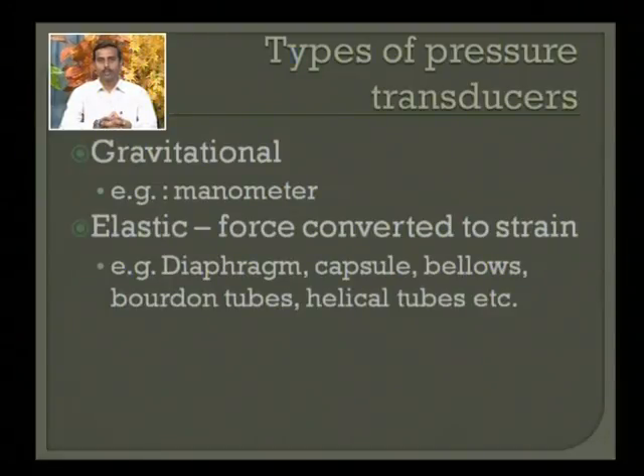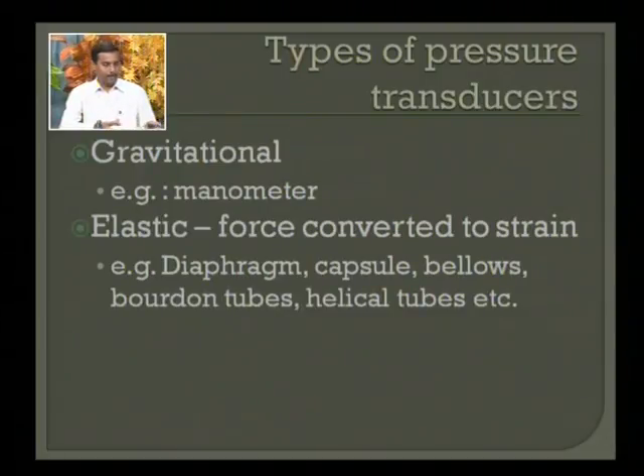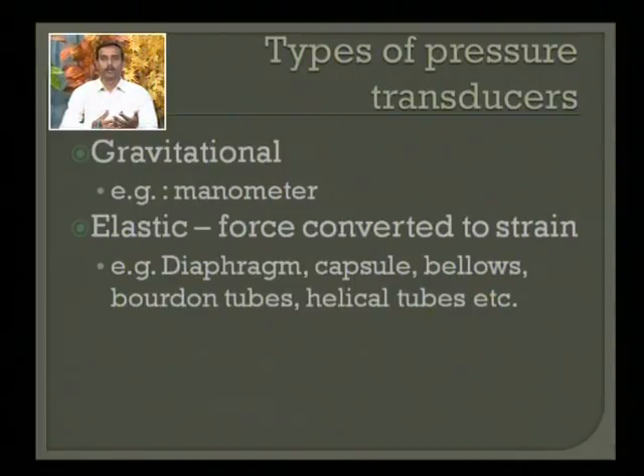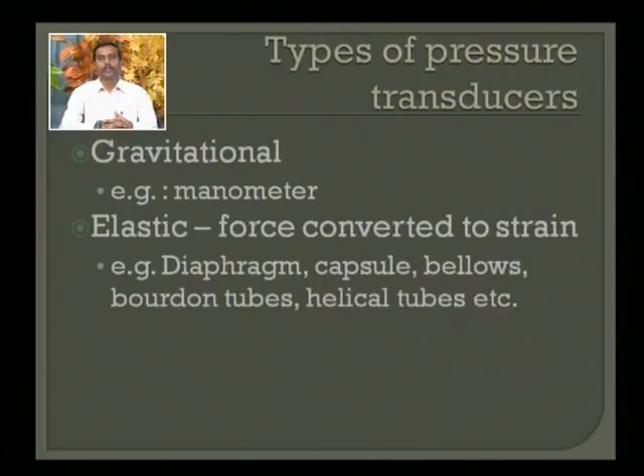Examples of gravitational measurement are manometers — either a U-tube manometer, inclined tube manometer, or cistern manometer. These manometers have a liquid filled in a tube that can be utilized for pressure measurement. In the elastic category, a force is applied to an elastic object and whatever strain is generated in that object is the measurement of pressure. Transducers of elastic type include diaphragm type, capsules, bellows, Bourdon tubes, and helical tubes.